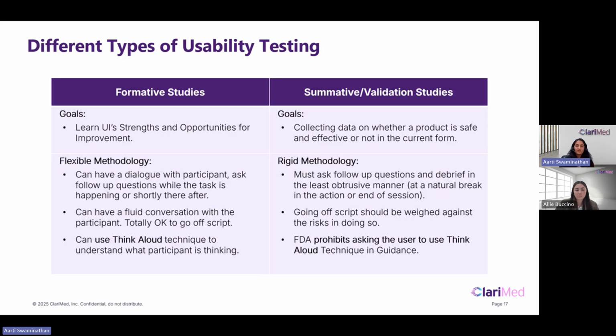And even ask them to do things like thinking aloud during the process to help you understand what their thought process is. Versus in the validation studies, there's a lot more onus to make sure that the structure of it is as representative of real life use as possible. The validation study is really intended to almost test out the worst case scenario: at the minimum level of training, at the minimum level of guidance, at the greatest variety in terms of background of users, in terms of their experience and so on. How well can they perform with your product?